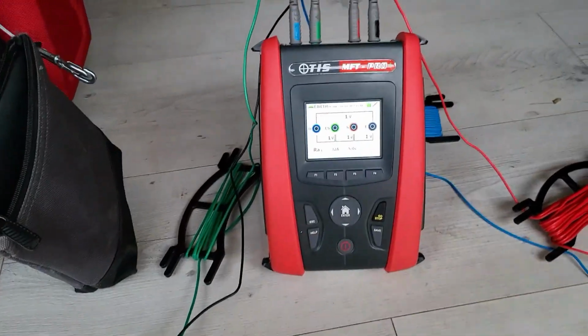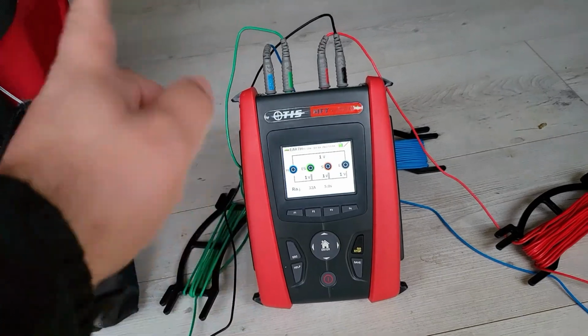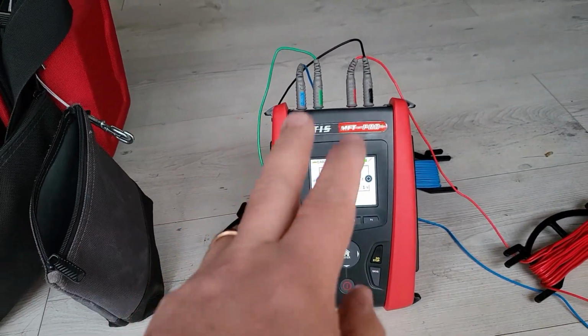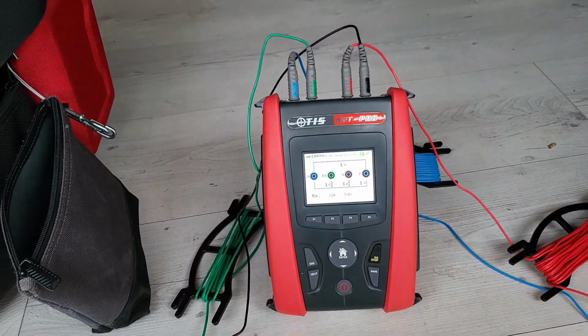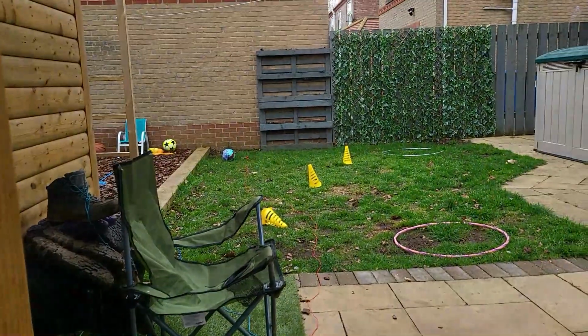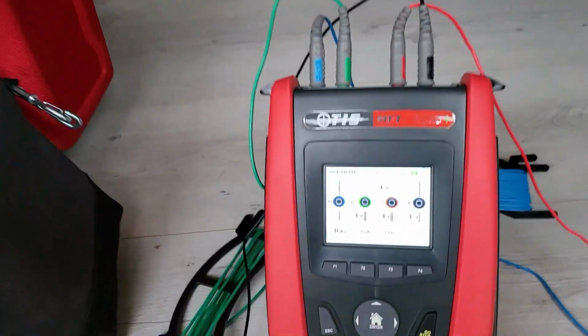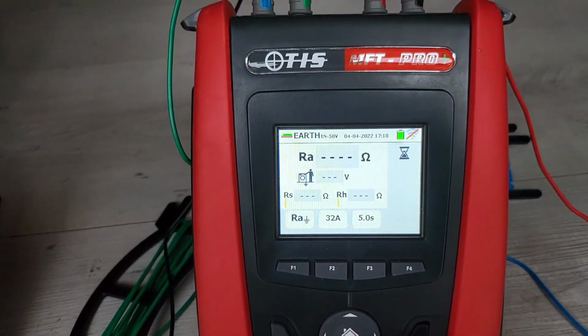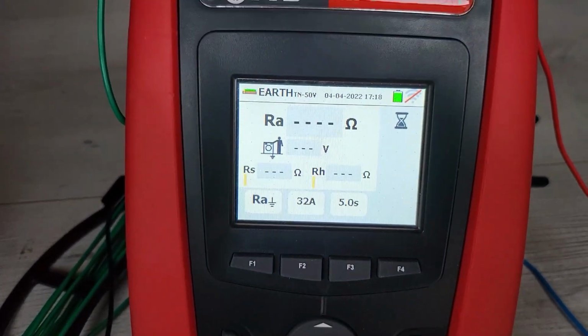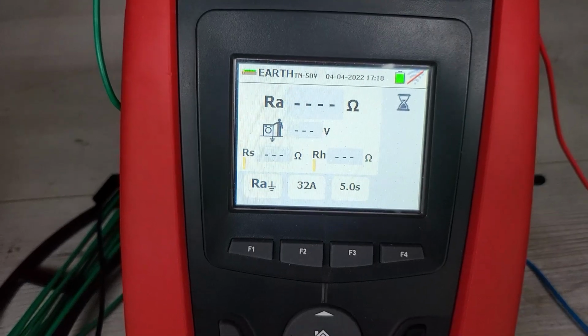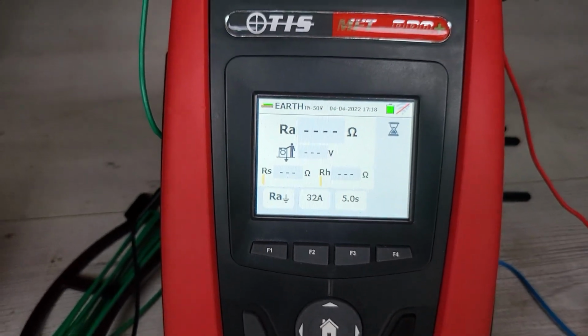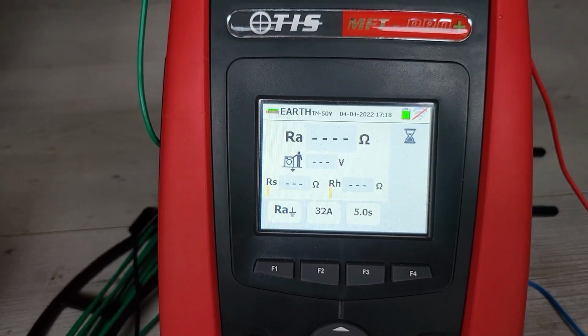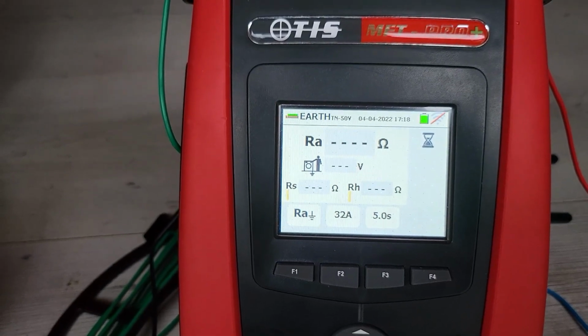We've got the test set rigged back up, and as I showed you on the other video, we have got the blue going out to the furthest spike, the green and black both going to the electrode itself, and then the red is the midpoint, which you can see I've got on that spike over there. So if we hit the test, and you will see it's having a good old think. You might be able to hear it clicking away there, doing its stuff.